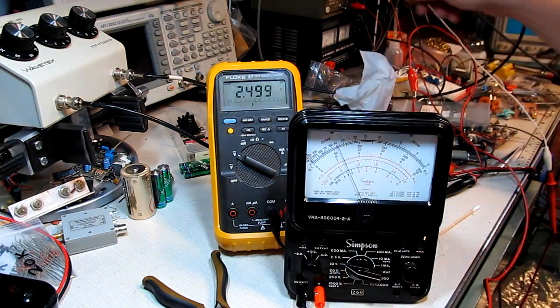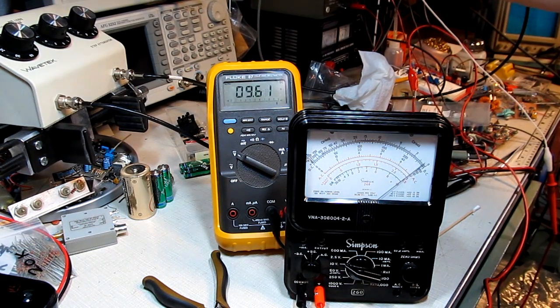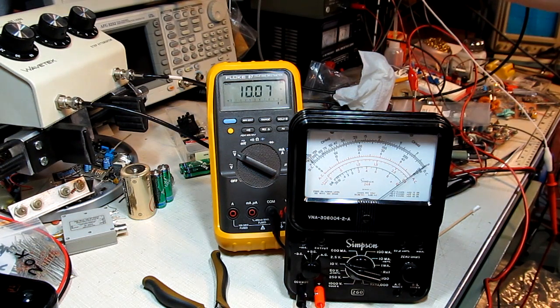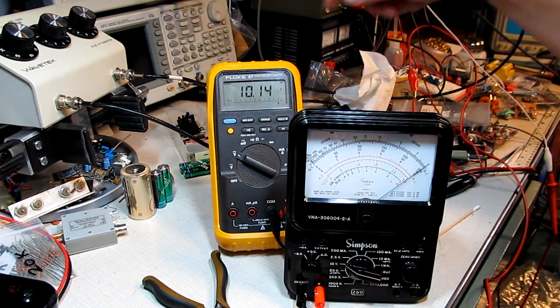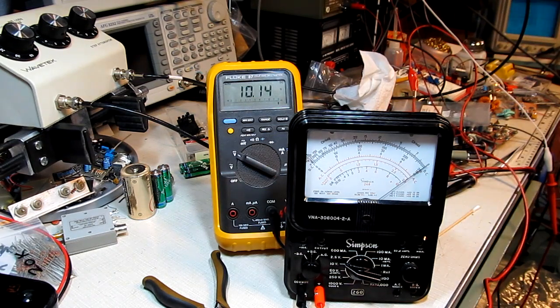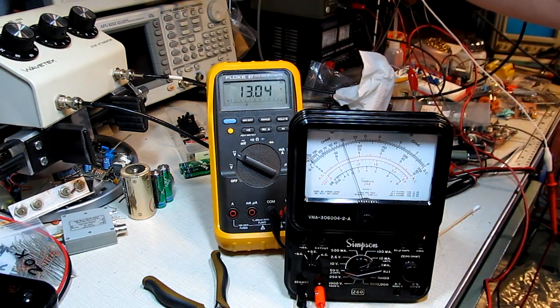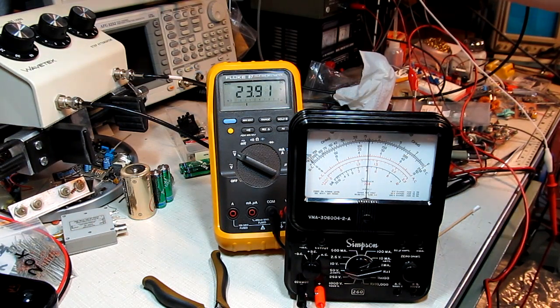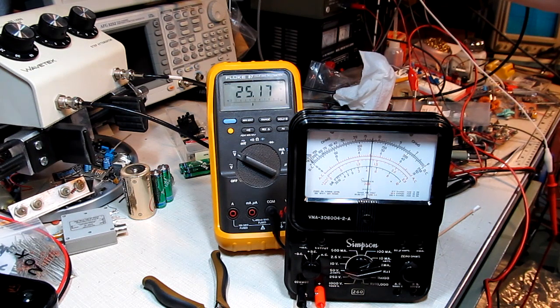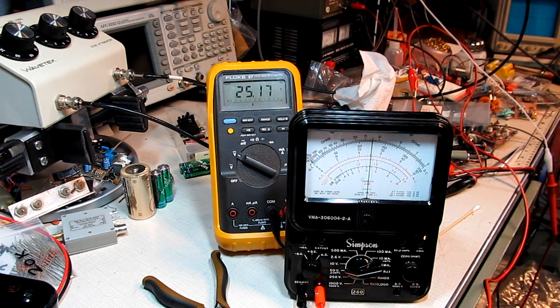If we adjust to the 10 volt scale here, let's turn the voltage up. On the 10 volt scale, let's bring this up to 10 volts. We're basically at 10 volts right there and I'm only about one percent high. That's certainly well within spec of what I'd expect for a meter of this age, so I'm not even going to worry about it. Let's go to the 50 volt scale and turn the voltage up here. This power supply doesn't go all the way up to 50, but let's bring it to mid scale at 25 volts. That's right about there. I'm at 25.1, 25.2, again about 1% off. I think that's pretty good for a meter that's probably as old as I am.